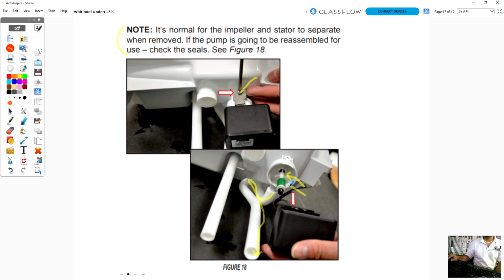This is the armature that the motor goes over, and that will stay there. You can replace this pump and motor assembly and leave that armature there. Note, when you're ordering a drain pump, it might or might not come with this. I haven't looked at the parts breakdown, but if you see this piece sticking up there when you take the motor out, don't think you broke it. That is normal.